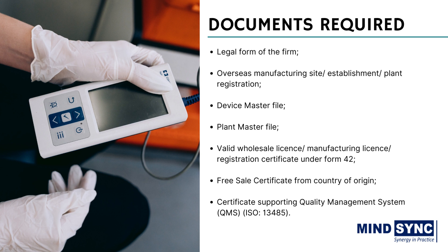A checklist of documents required for grant of import license includes: legal form of the firm, overseas manufacturing site or establishment or plant registration, device master file, plant master file, valid wholesale license or manufacturing license or registration certificate under Form 42, free sale certificate from country of origin, and certificate supporting quality management system under ISO 13485.